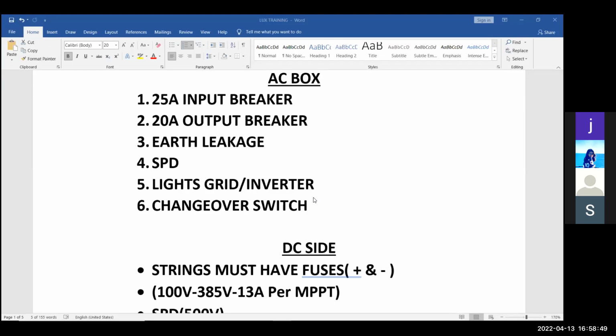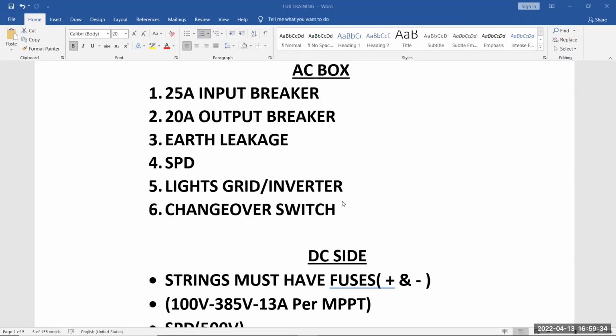the reason we don't like the inverter to trip under load. So that means when you don't have Eskom, this inverter is capable of giving you 5 kilowatts worth of backup power if Eskom is not there at the moment. Then you can get 5 kilowatts of power. But if you go over 5 kilowatts of power, the inverter will trip. And it is not a healthy thing for your inverter to keep on tripping. It's rather safer for a 60-70 Rand circuit breaker to trip than your inverter. So that's why we have a slightly smaller output breaker than what the inverter can give you. So your circuit breaker will trip and not your inverter.